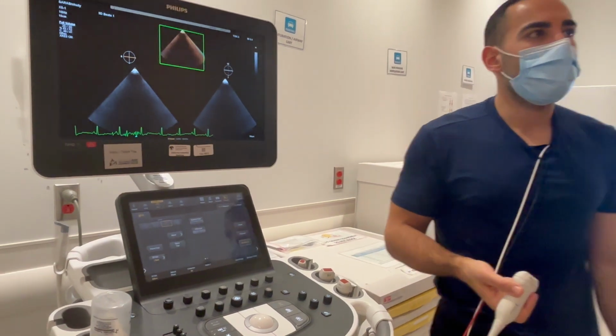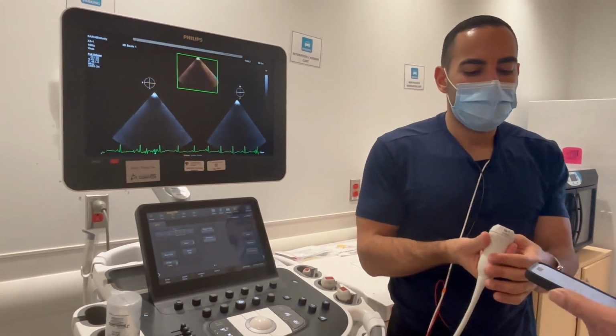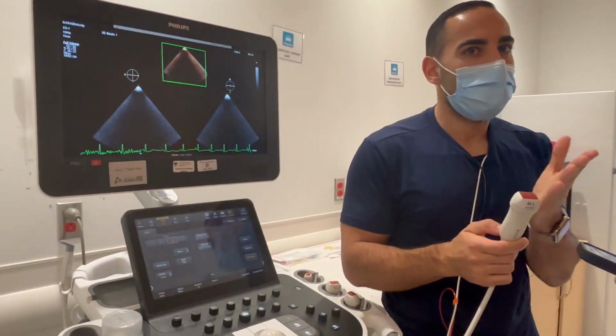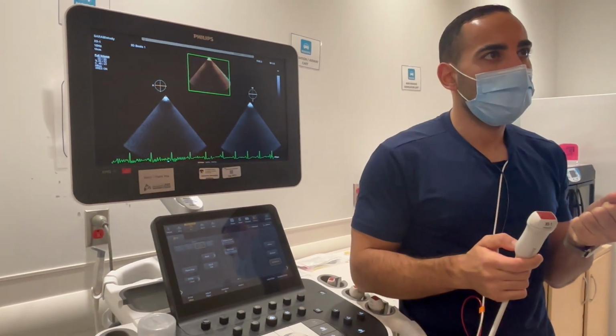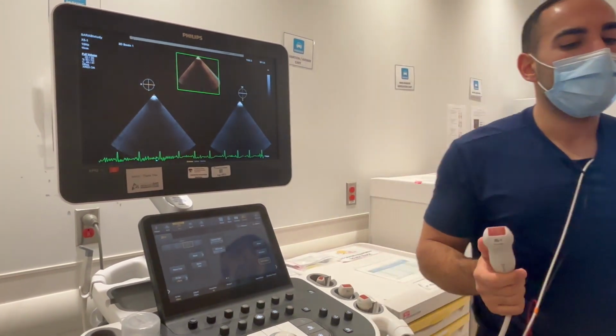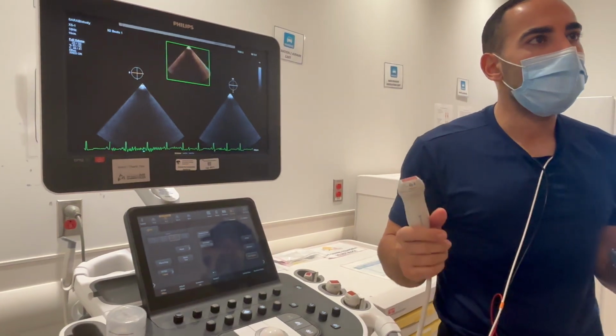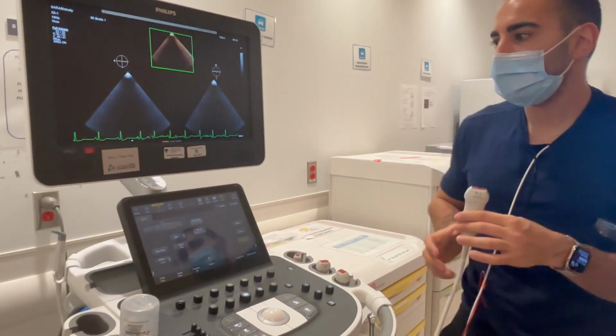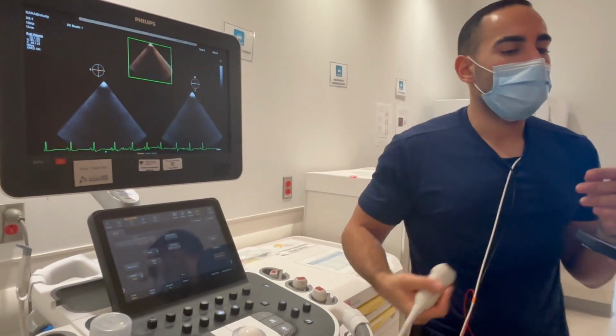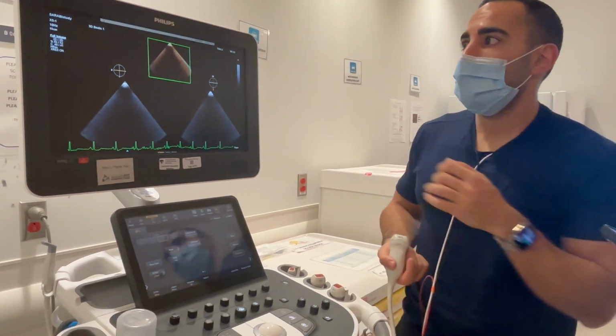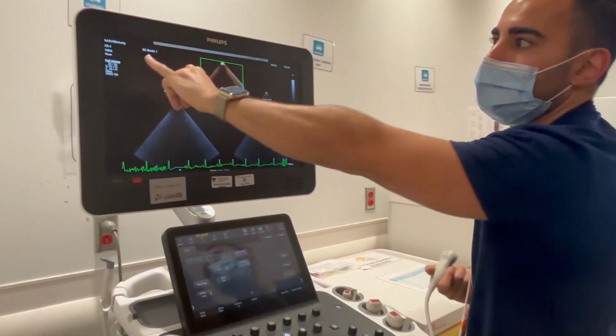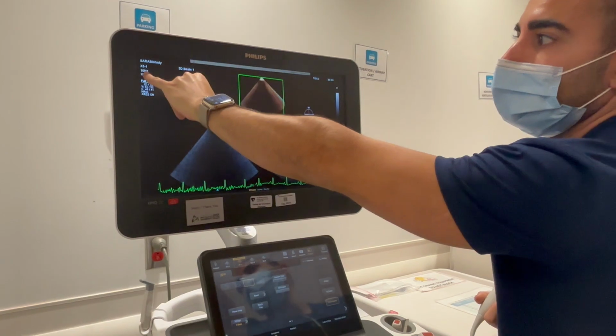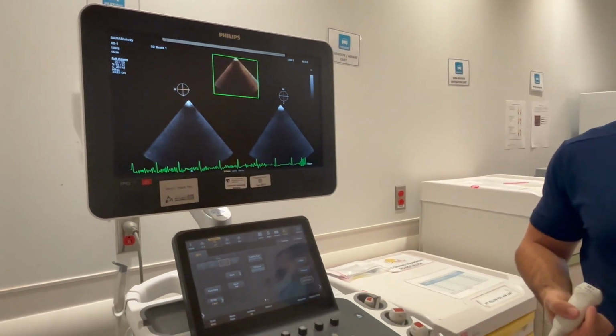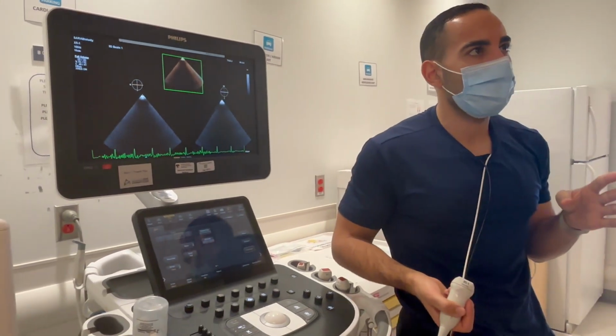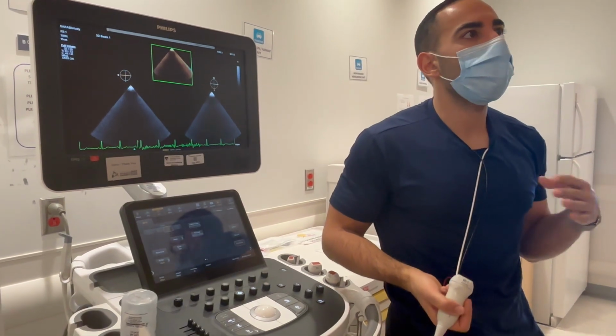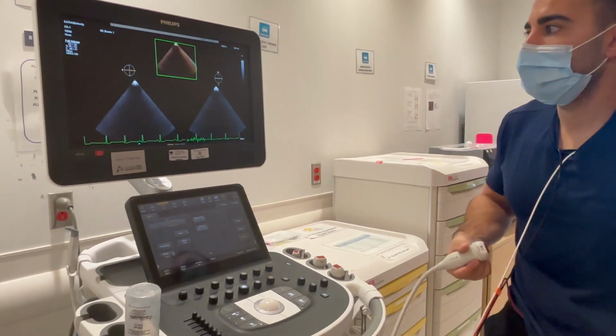Philips has two ways of acquiring 3D. It can acquire 3D by sending planes of ultrasound waves in different directions to increase the temporal resolution, or it can do multiple capture beats where it fuses different beats together. What we want is one of each, okay? On the image, you have here the frames per second, or the hertz. It tells you 10 hertz. To do 3D volumes, I need at least 28 to 30. If I have less than that, I won't be able to reconstruct the volumes.